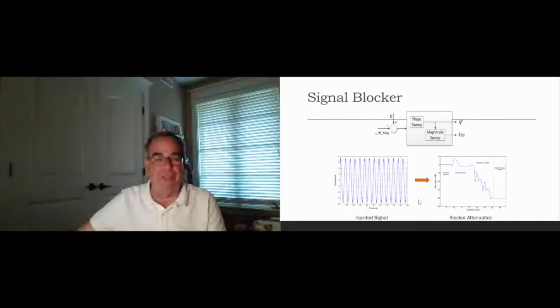So we'll start building the hardware that could actually be used to clamp onto a cable and so on. The way it would work in the field is you'd go to two manholes, put the injector in one and a blocker in the other, and then you test the cable between those two points. Very simple. Here's our guys at the University of Akron working on cables that were provided by American Electric Power. This is our phase one, which was the model development. And you see the team there working.